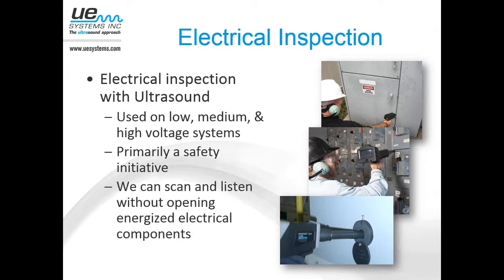Infrared is really geared to pick up resistance-based failure modes, while ultrasound picks up ionization-based failure modes. There's plenty of examples and gear where you're only doing half the job if you rely 100% on infrared to find all the failure modes. So many companies, and especially many service providers, have started to employ ultrasound hand in hand alongside their thermography program, with great results.